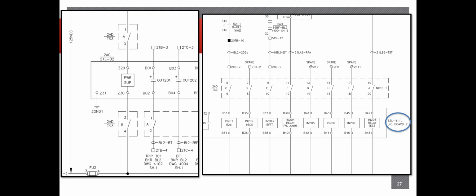So we've got a little zoomed in picture of the relay schematic. We've got the identifier, which is that top left circle right there. We know it's going to be in panel 2 in position AC, as well as the unique identifier. The unique identifier is very client dependent. Everyone has a different way of identifying their equipment, whether it's kept track of by the relay type. For this example, you could almost assume that it's going to be a 421, based on that, but it's actually a 411L because it's going to be a line relay code, as well as B2, which could stand for backup or backup 2, for example. You should understand which client you're working for, understand their standards and the way they name a certain piece of equipment, and it'll help you in the process when you're troubleshooting, especially.